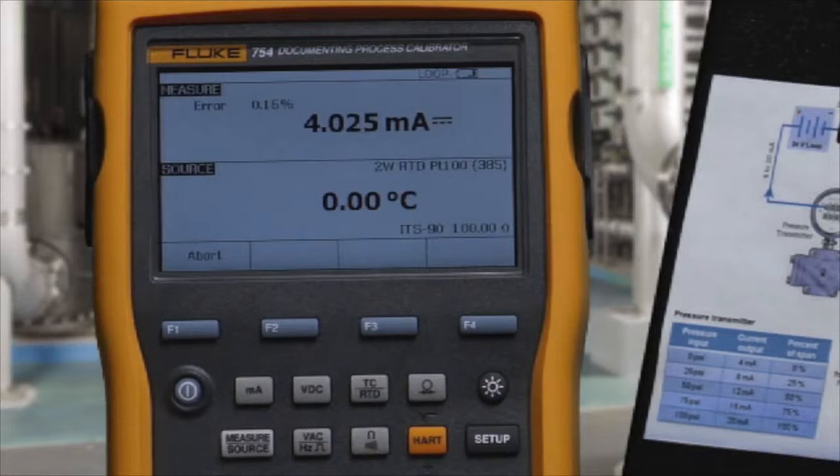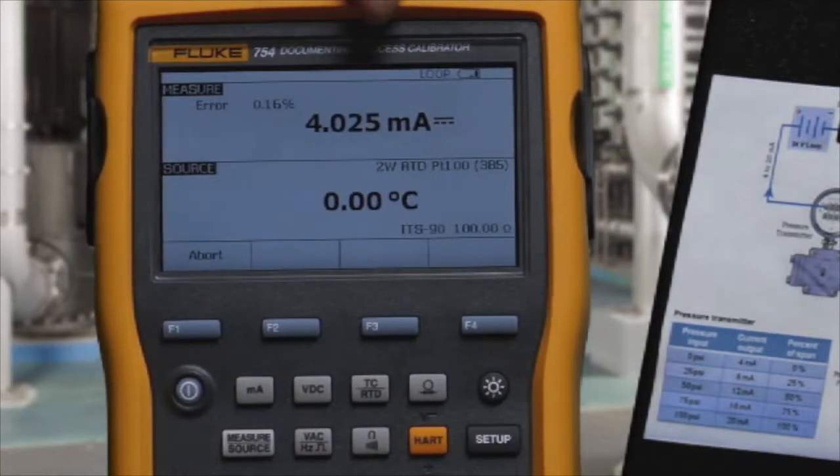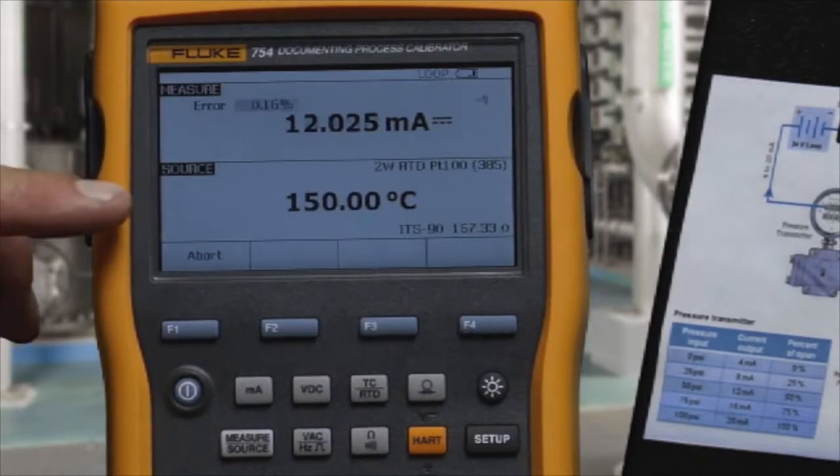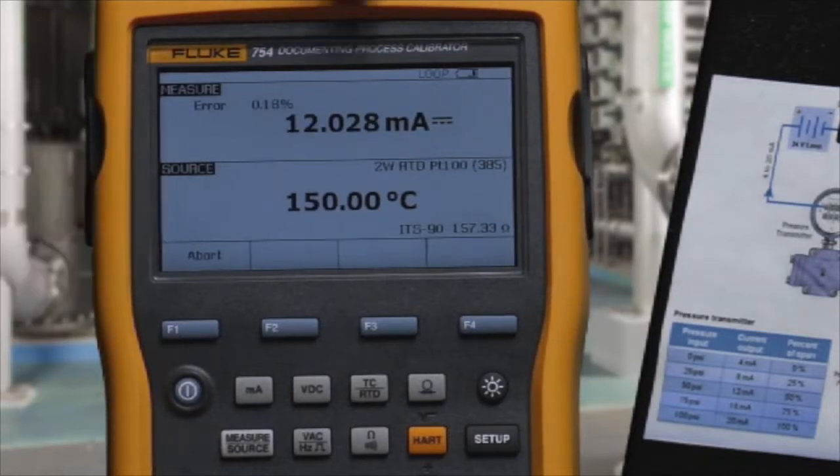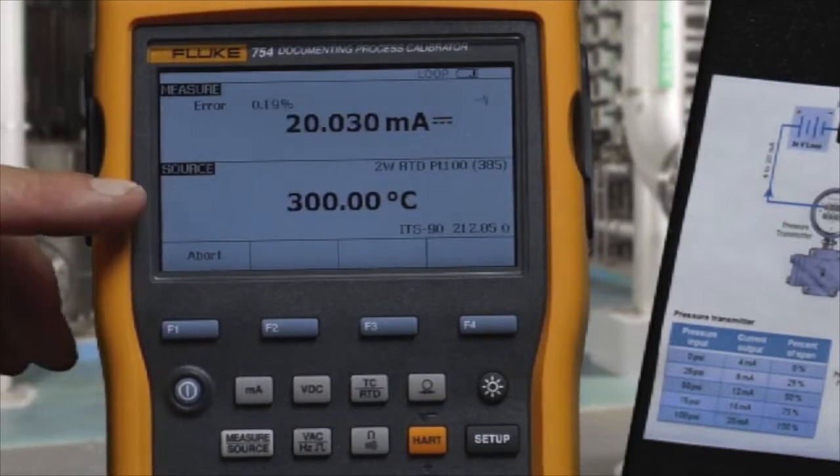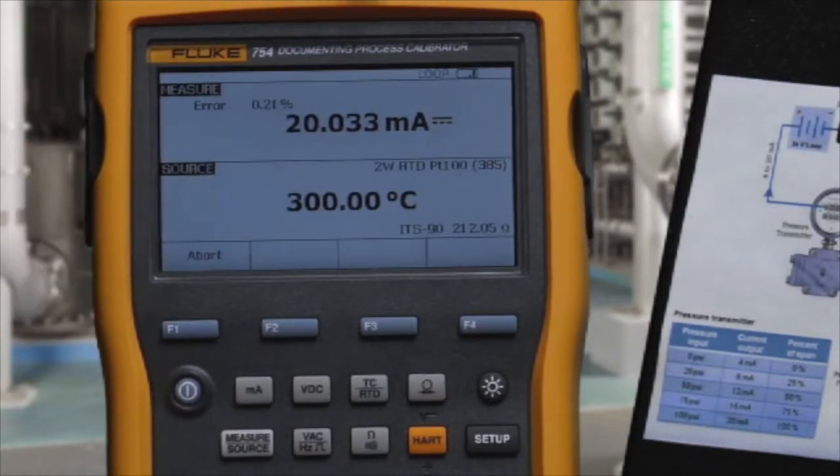0%, 4 milliamps is being measured, error percent is being calculated. The 50% value is applied, milliamp measured, and error percent being calculated. Then the 100% temperature value is applied, milliamp value is measured, and error percent is calculated.